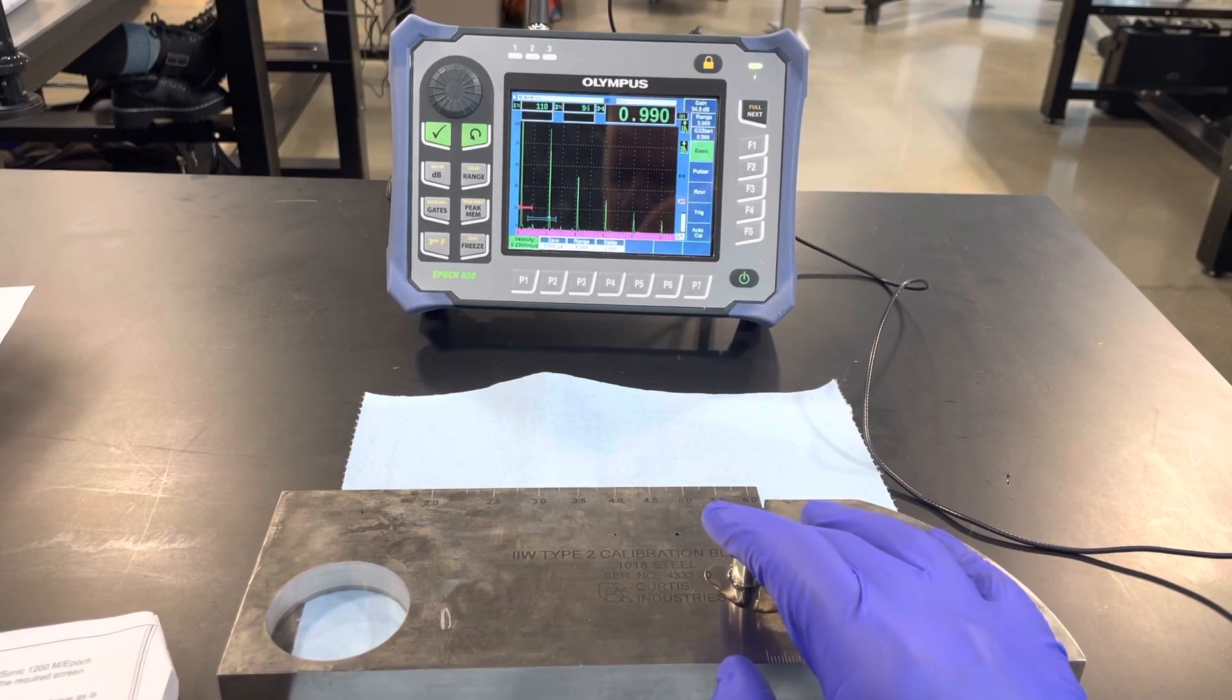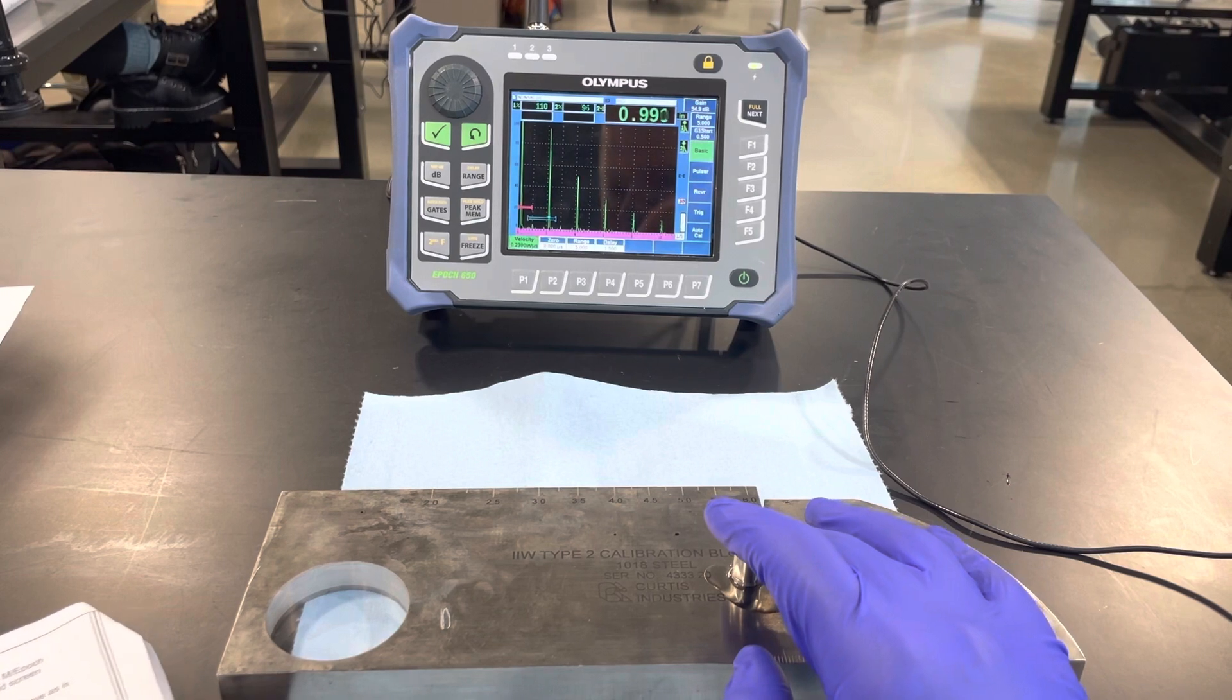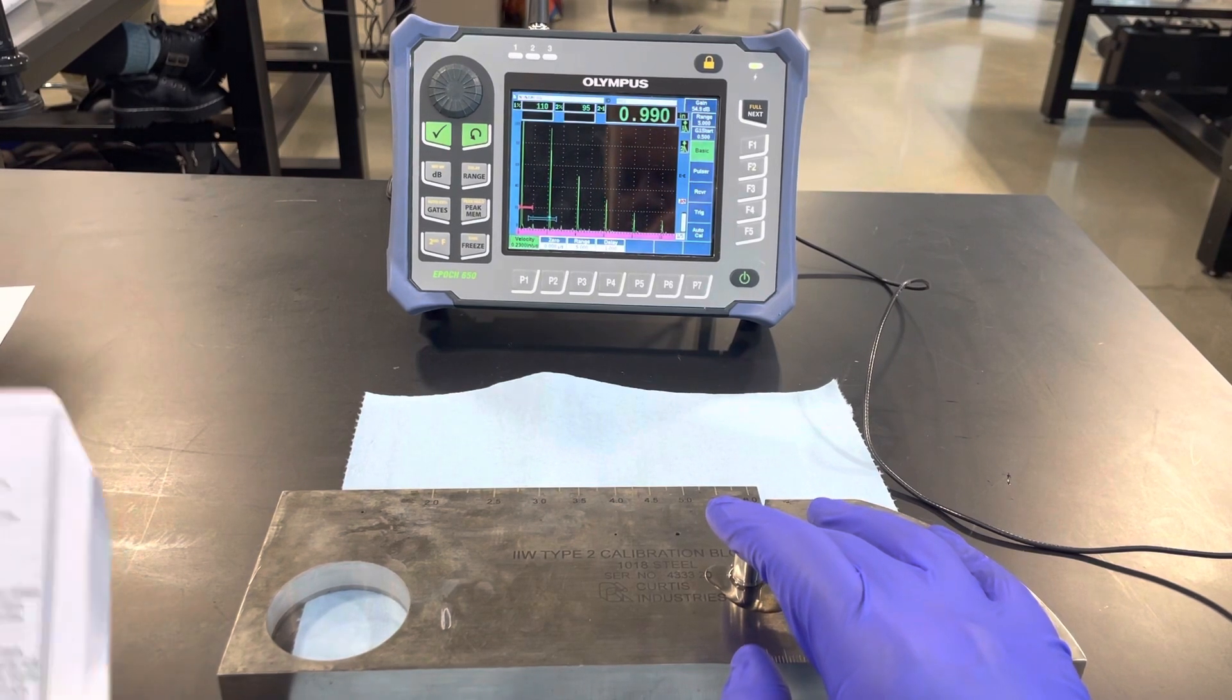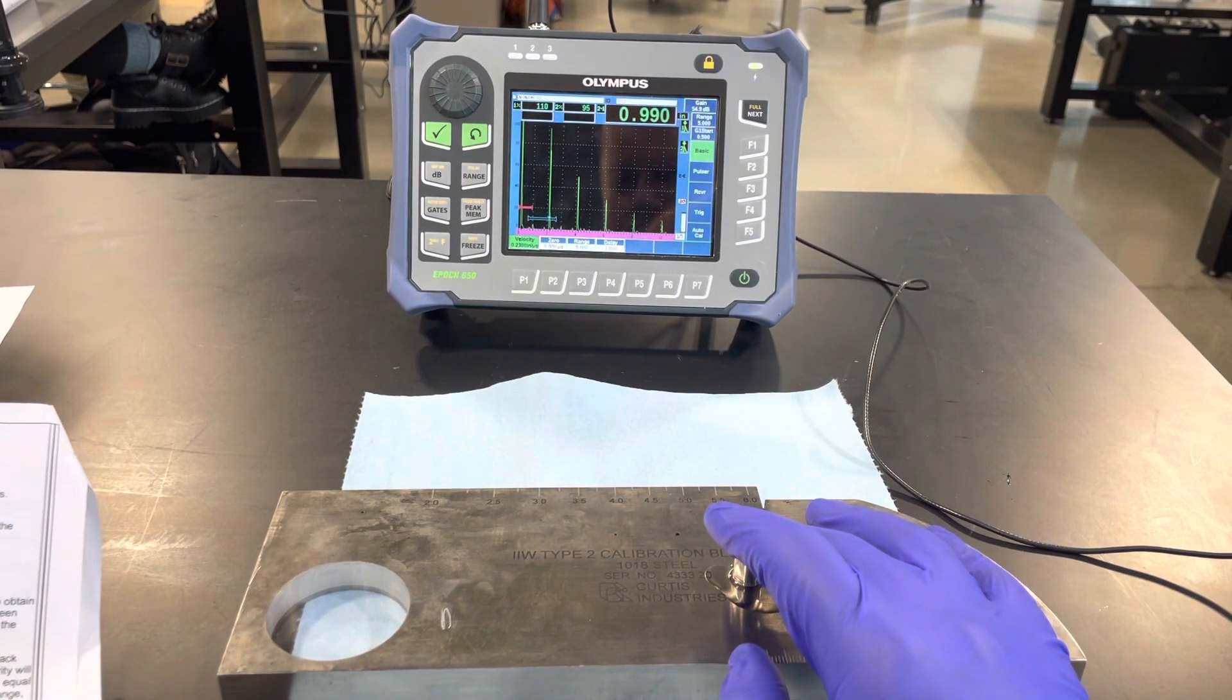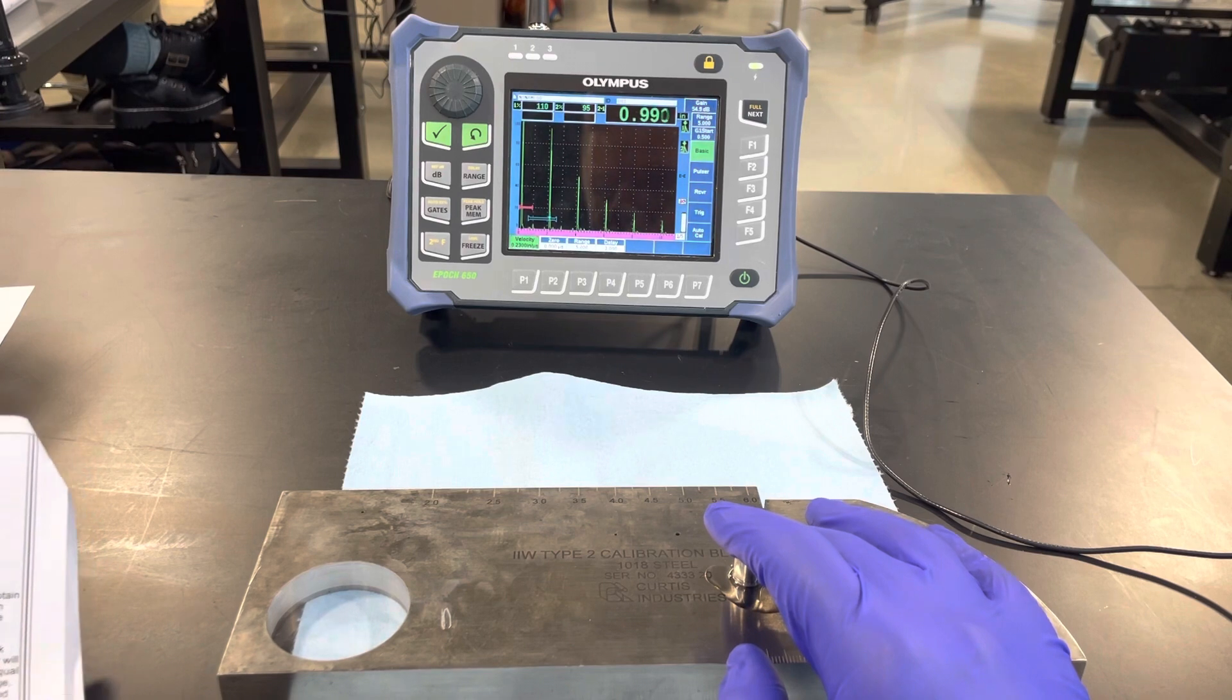Alright, here we are doing a horizontal linearity check with a 5 MHz transducer and a steel type 2 IIW block.